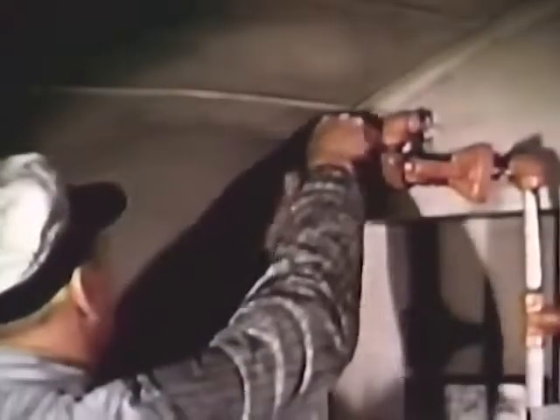Prepare the CO2 system for action by first opening the pull box and pulling the handle hard as far as it'll go. Second, throw valve handle to the left at the hose station to be used. Third, run the hose and discharge horn to the fire. Since each pair of cylinders lasts only about a minute, don't squeeze the handle until you're ready to put out the fire.